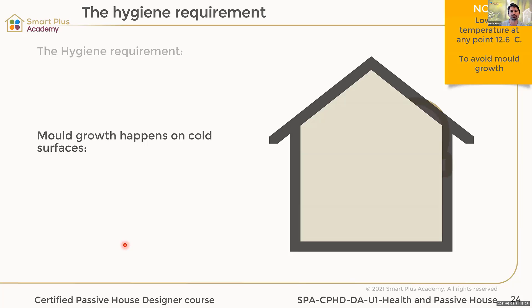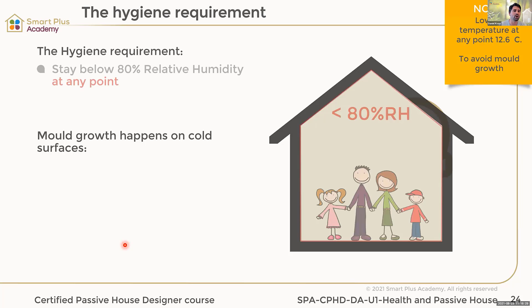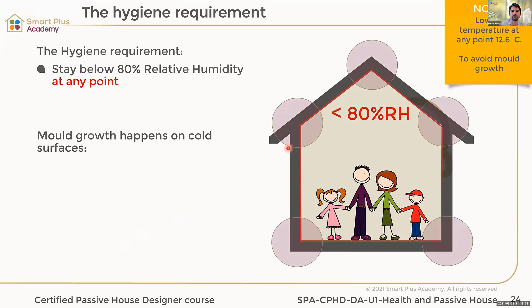The hygiene requirement is to stay below 80% relative humidity at any point. We're speaking here about the points that are colder in the cold climate, and that's where we're having our mold issues, to avoid mold problems.